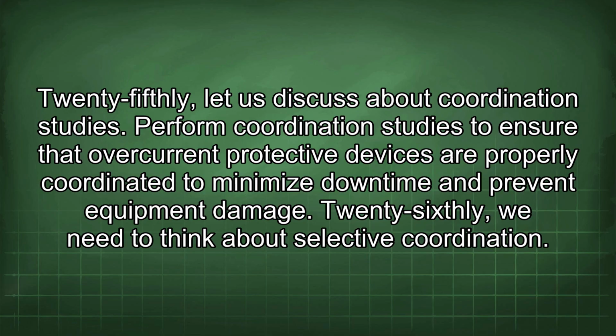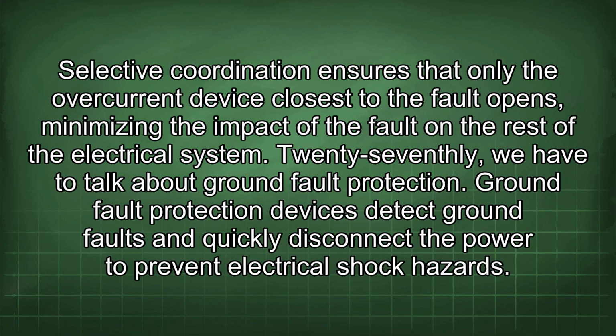25thly, let us discuss coordination studies. Perform coordination studies to ensure that overcurrent protective devices are properly coordinated to minimize downtime and prevent equipment damage. 26thly, we need to think about selective coordination. Selective coordination ensures that only the overcurrent device closest to the fault opens, minimizing the impact of the fault on the rest of the electrical system.